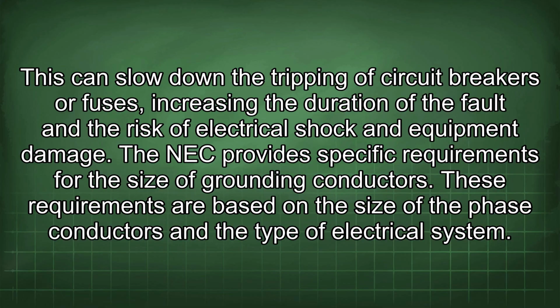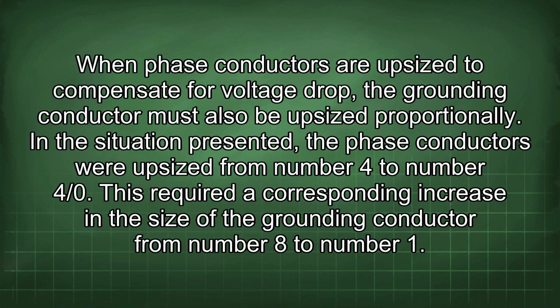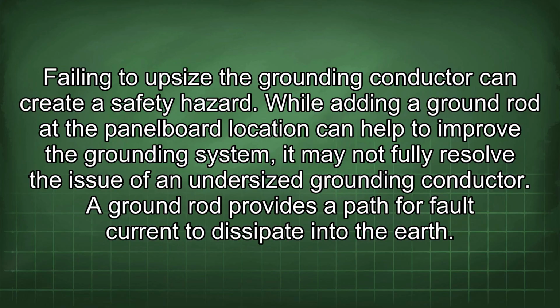The NEC provides specific requirements for the size of grounding conductors. These requirements are based on the size of the phase conductors and the type of electrical system. When phase conductors are upsized to compensate for voltage drop, the grounding conductor must also be upsized proportionally. In the situation presented, the phase conductors were upsized from number 4 to number 4/0. This required a corresponding increase in the size of the grounding conductor from number 8 to number 1. Failing to upsize the grounding conductor can create a safety hazard.